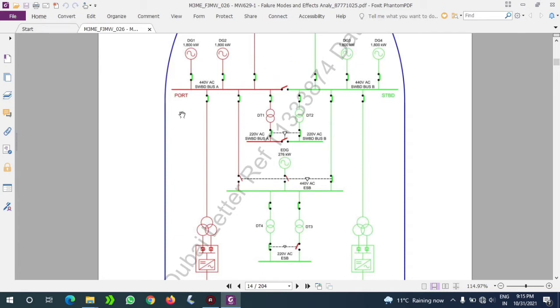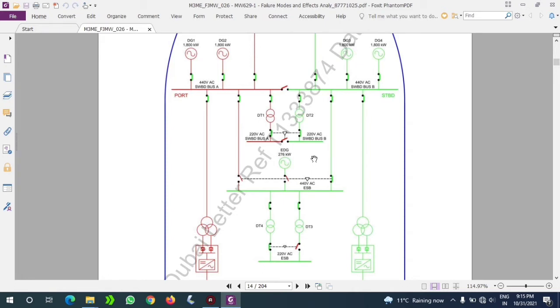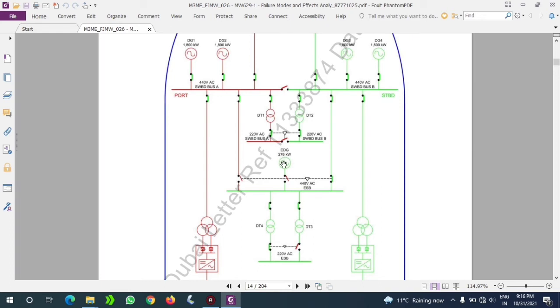What is the capacity of emergency generator here? You can make out it's 276 kilowatt. You should always see our other generators are of 1800 kilowatt and our emergency generator is only 276 kilowatt. What may be the reason? Because we need emergency generator to supply only the essential consumers. We are not going to run the emergency generator for thruster motors.